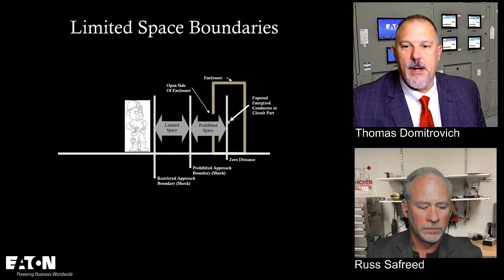Now the arc flash boundary. This is where the rubber meets the road in this discussion. So what we do is we run a calculation, and we typically calculate the working distance, 18 inches, and what your incident energy values are, and that's arm's length away from the exposed conductors. But to establish the arc flash boundary, it's an iterative process of putting different distances into the calculations for incident energy until you get to 1.2 calories.